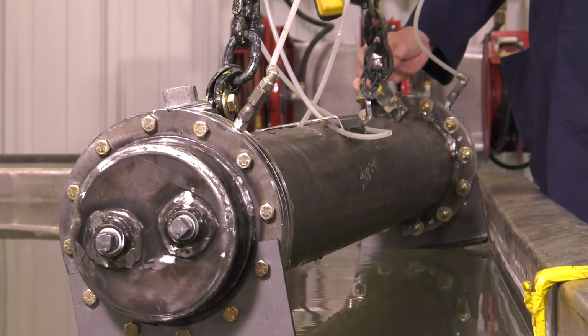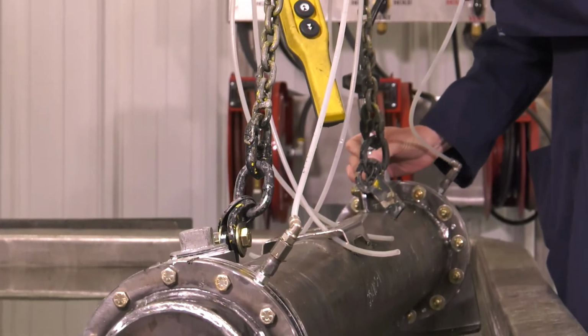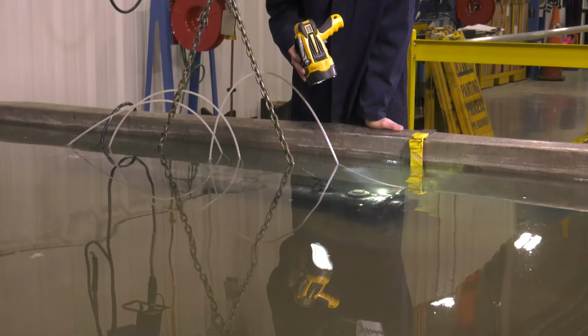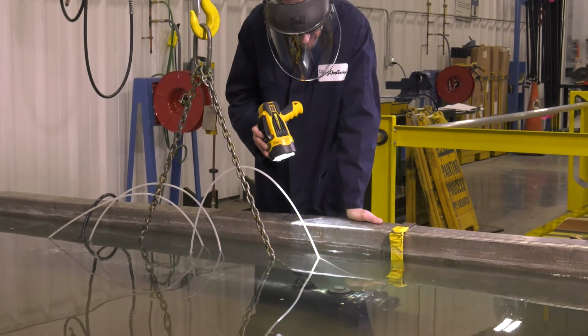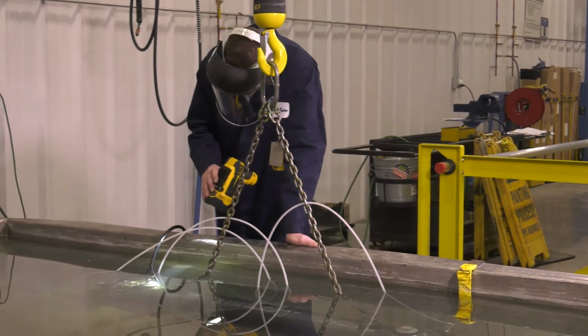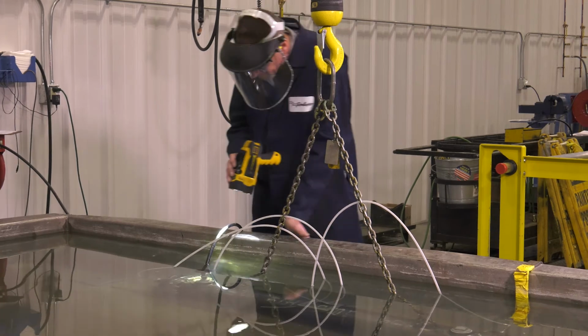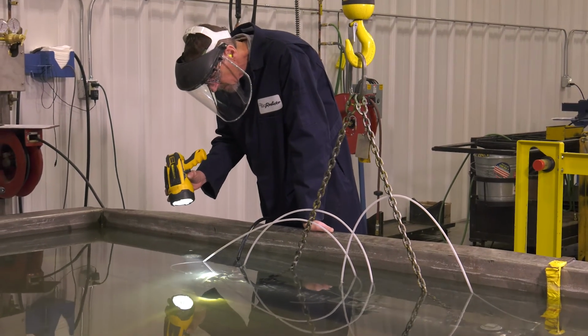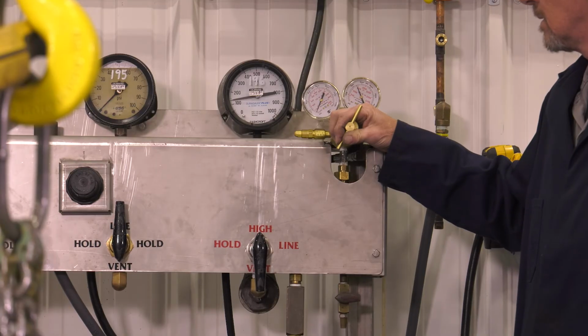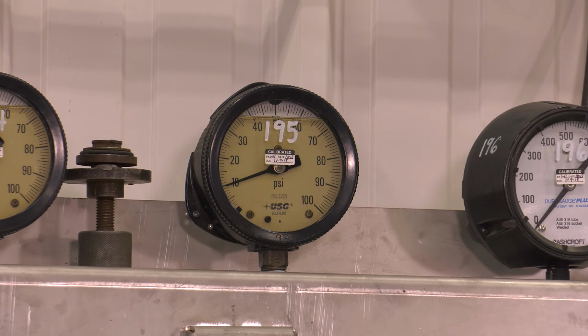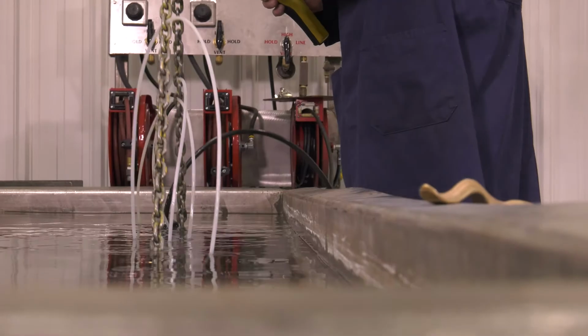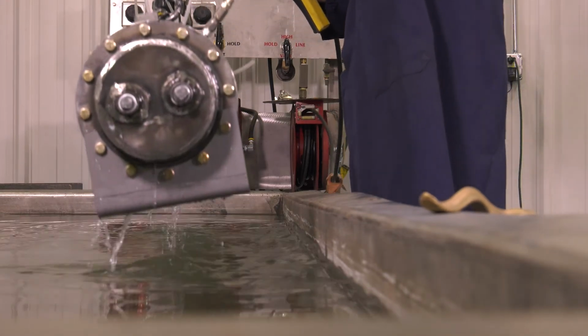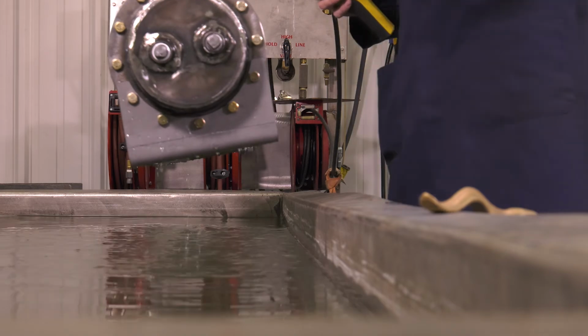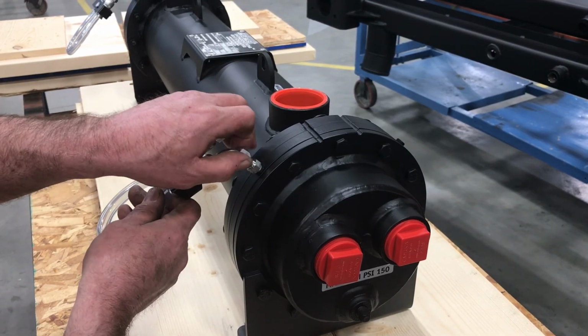To test the tube side, typically the water side, follow the pressure cycle steps in the System Protector Service Manual. Begin the sequence of pressure cycles as stated in the System Protector Service Manual. Check for leaks at the detection port. If a leak is detected, it should be an outer LS or LT seal. Repair as required. After any repair, restart the test sequence at step 1 and continue until the sequence of pressure cycle tests has been completed. Remember to dry the detection chamber after testing. Dry it from the sight tube detection port by removing the plug opposite the sight tube. Once dry, install the sight tube assemblies.